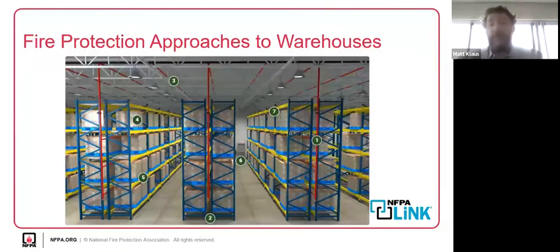Based on a choice by the owner, we might have solid shelving, requiring in-rack sprinklers, seen on node 1, where we actually put the sprinkler close to the potential fuel source because of the hazard it carries. We've got to know this going in, since the hazard might dictate where the sprinkler is and how much water I'm going to need. So automatic intervention is one thing.